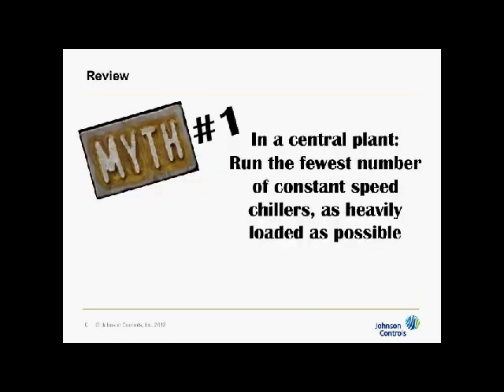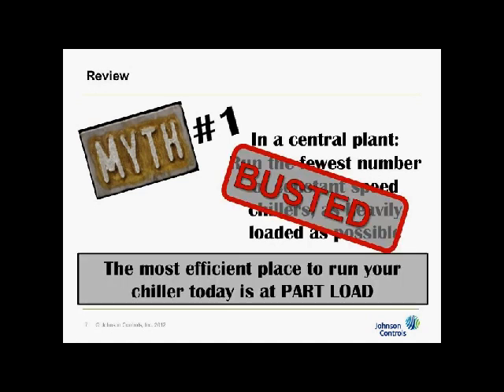The 5 myths from last time, if you were at that webinar in August. Myth number 1 is, in a central plant, you should run the fewest number of constant speed chillers as heavily loaded as possible. Generally speaking, this appears to be correct, and quite often is, because the auxiliaries are usually not controlled with variable speed drives, and all of them, and with optimization algorithms. If that's done, then it is cheaper to run 2 chillers than 1, whether they're constant or variable speed. Again, the same rules apply, that you need to be at lower head when you do that. So that myth was busted last time.